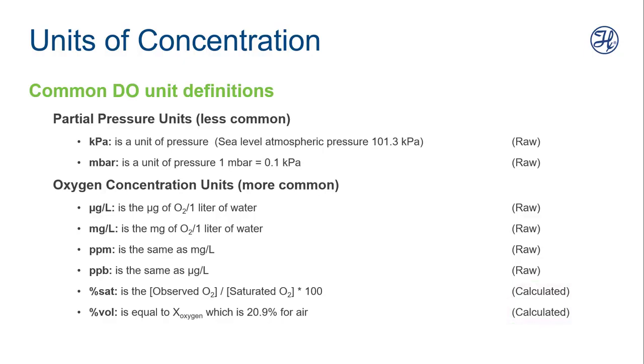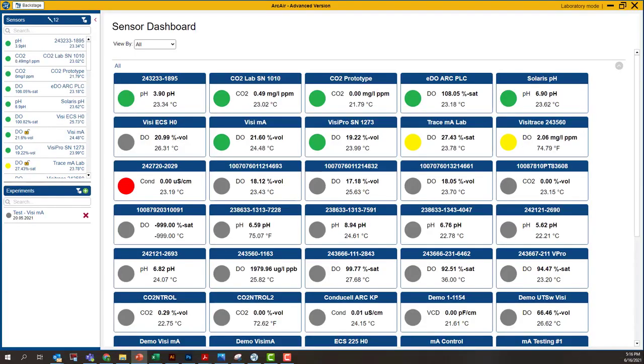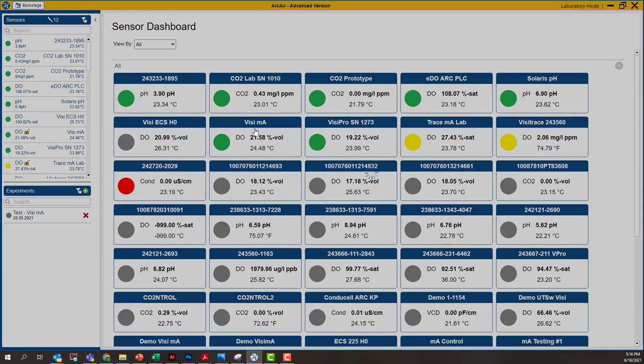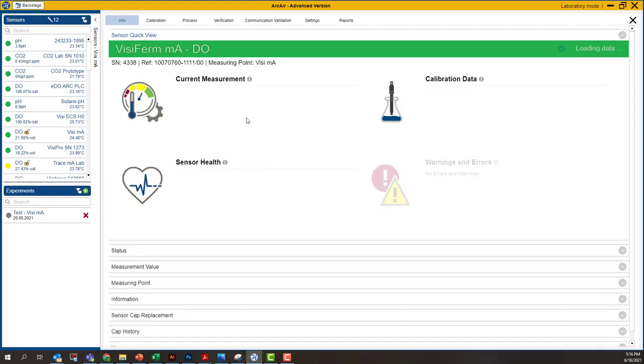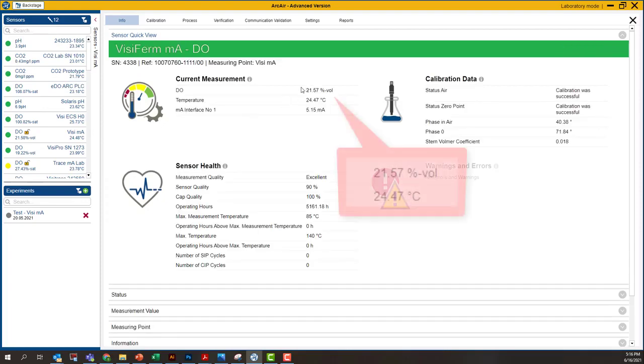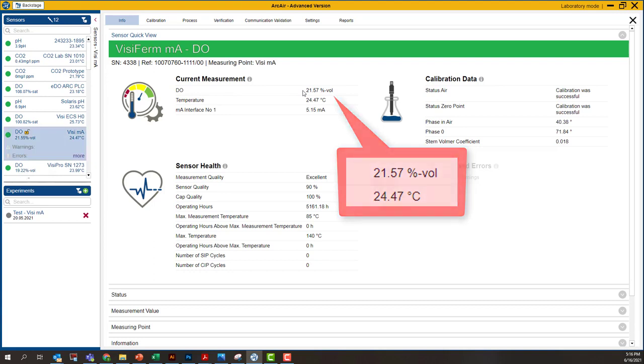So what does that mean? Well, let's actually take a look at one of our sensors here to help understand. I'm going to click into this VisiFerm mA I've got set up here. This sensor is currently reading around 21.6% by volume. And please note, I haven't gone through a calibration on this. But that's about what we would expect as far as oxygen in air, and the sensor sitting in air.